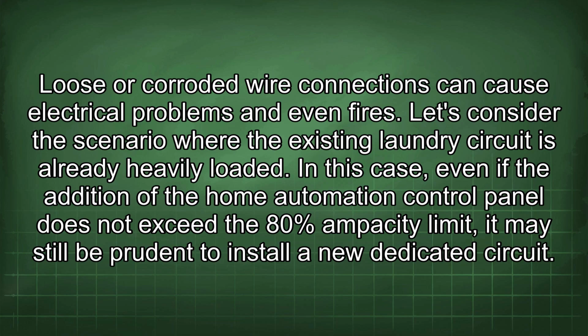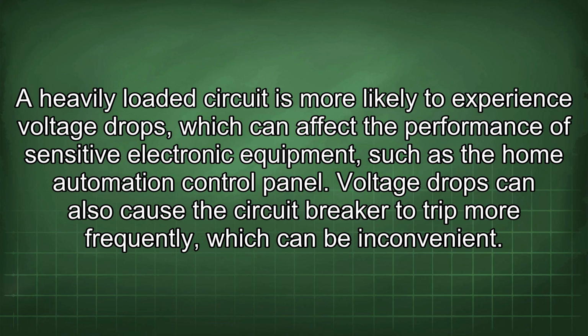Let's consider the scenario where the existing laundry circuit is already heavily loaded. In this case, even if the addition of the home automation control panel does not exceed the 80% ampacity limit, it may still be prudent to install a new dedicated circuit. A heavily loaded circuit is more likely to experience voltage drops, which can affect the performance of sensitive electronic equipment, such as the home automation control panel. Voltage drops can also cause the circuit breaker to trip more frequently, which can be inconvenient.